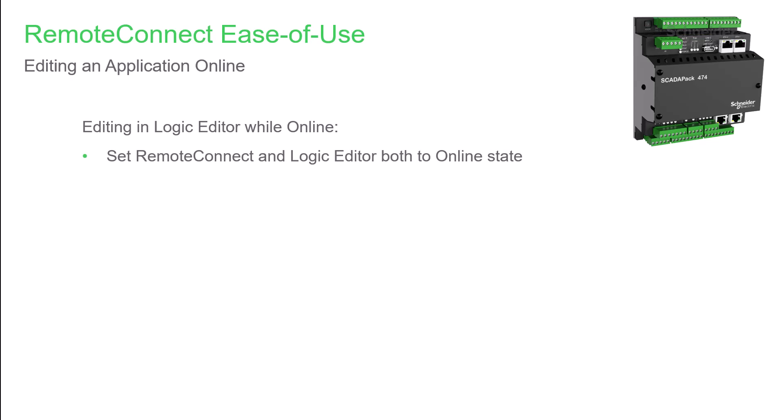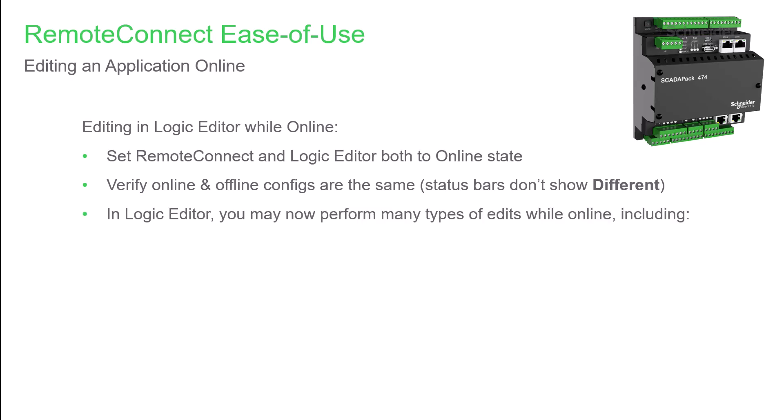Now let's move on to editing logic in Logic Editor. First, as with adding objects, put RemoteConnect and Logic Editor online. Next we'll verify that the online and offline configurations are the same by verifying that you don't see 'different' in either status bar. Now in Logic Editor, you can begin editing.